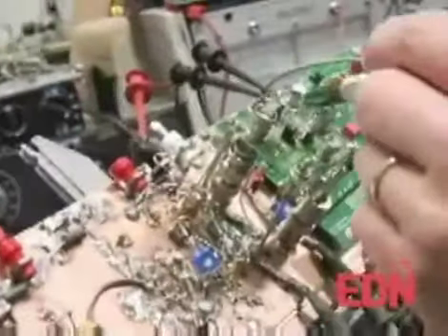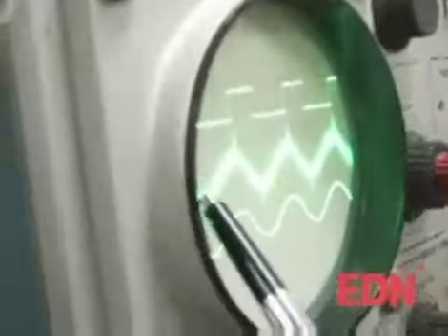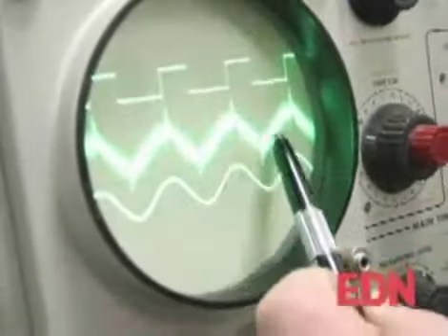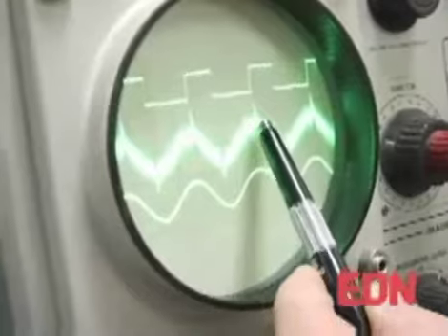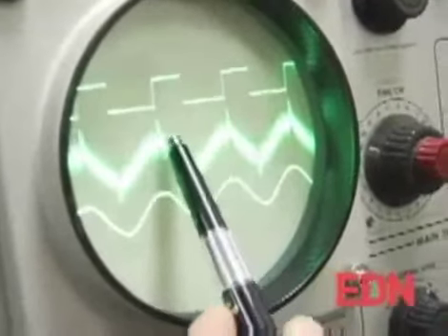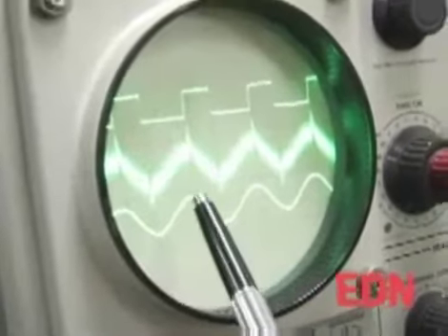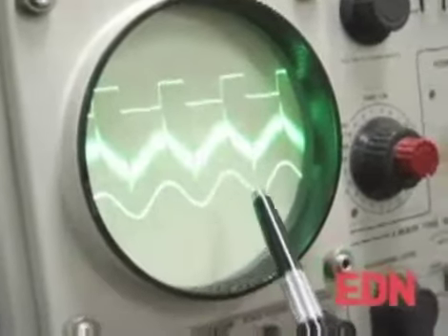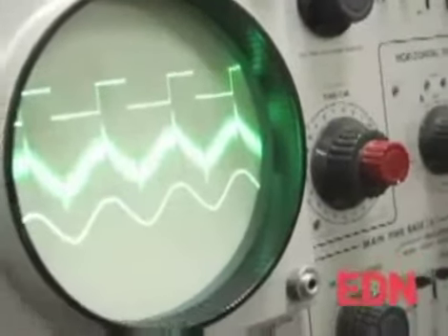This is the bandpass filter, and this last green board out here on the end is the RMS converter. This signal here is what comes out of the end of the gain chain before we go into the bandpass filter. That's the crystal current. The peaks here are differentiated response of the crystal holder itself and various shunt paths across the crystal. This is the output of the bandpass filter, which is sinusoidal.